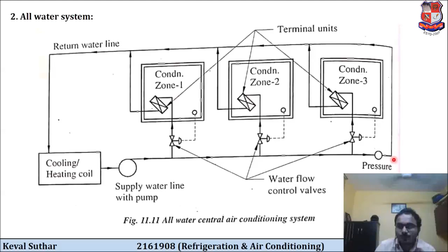Now this is the FCU terminal unit, that is called fan coil unit. You can see here an inclined box. In this terminal unit, if you see at the bottom, we are having warm air which is coming from the air conditioned space. Here we have provided an air filter which will prevent any impurities entering this unit. Here we have provided this fan, and then the important part is this finned tube cooling coil, through which the cold water is passing.